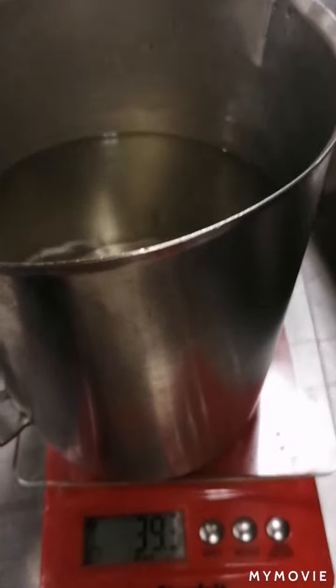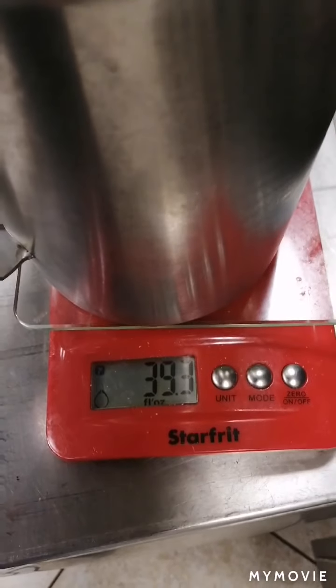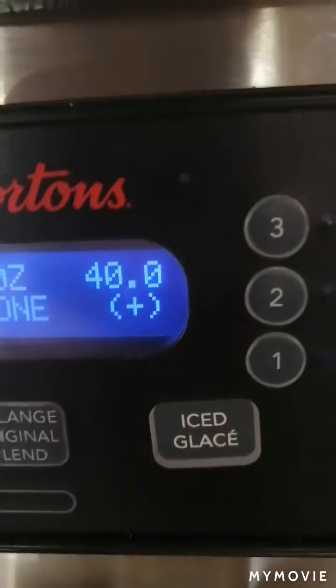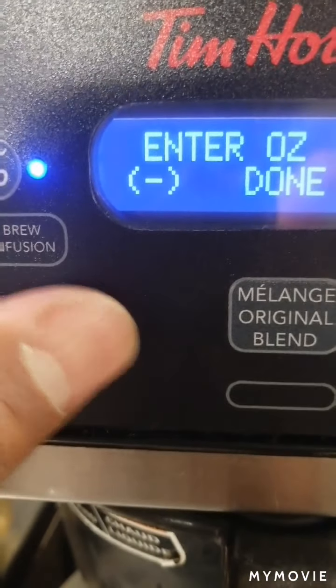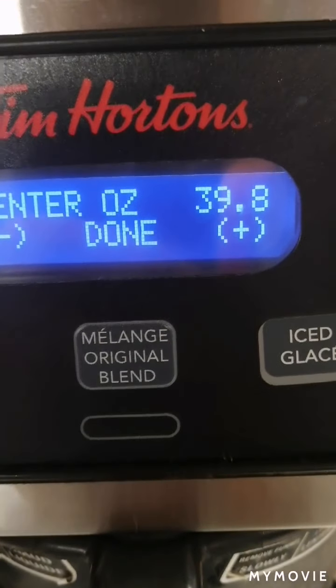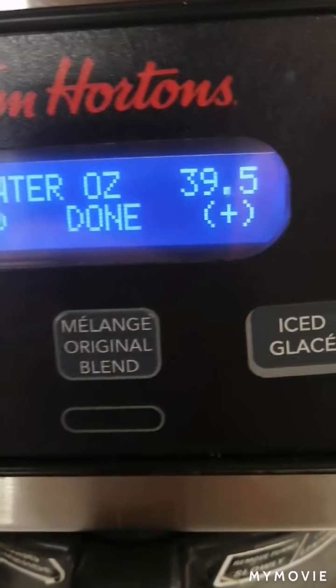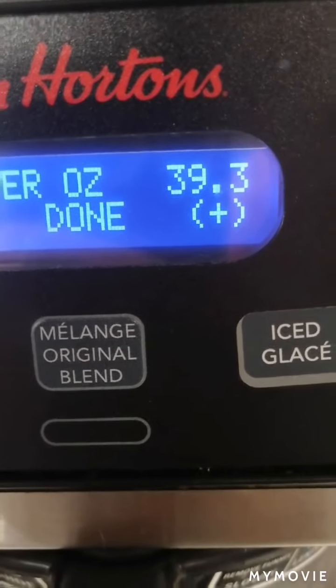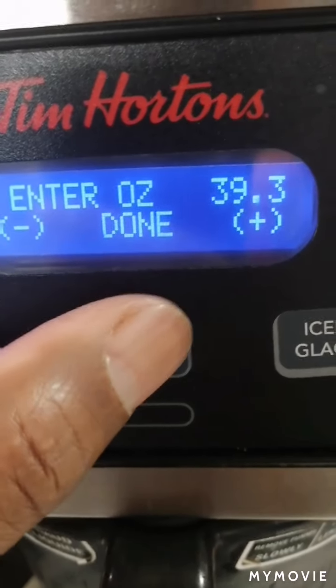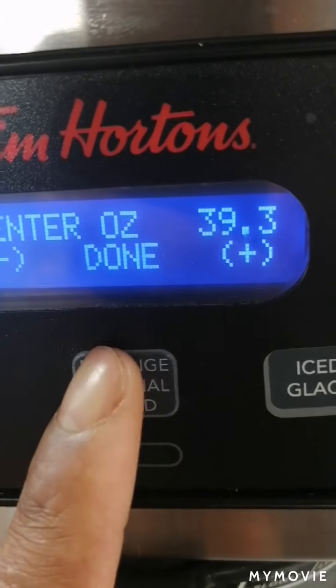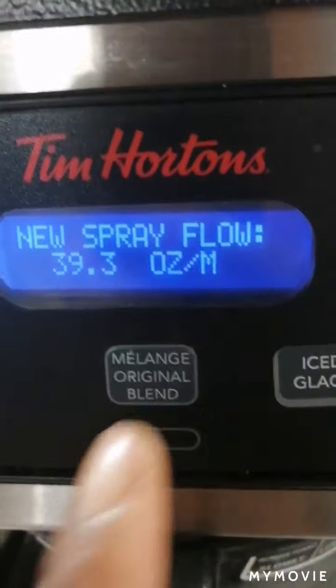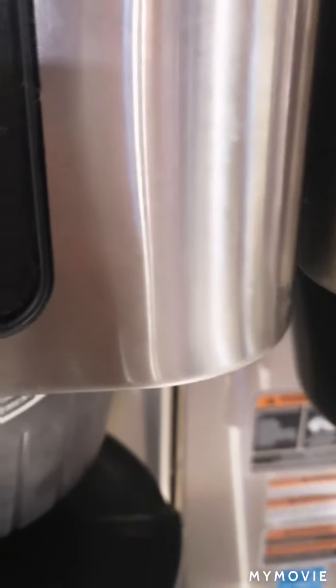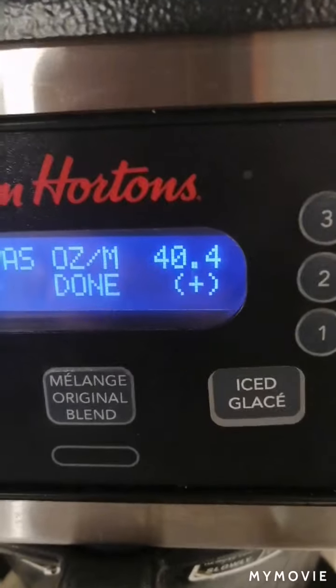So the scale is telling me that it gives 39.3 ounce, and that's fluid ounce, and the machine is telling me that it gives 40 ounce. So I need to minus. I'll hold this button down, there you go, 39.8, 39.7, 39.6, 39.5, 39.4, 39.3. So I get that amount that I have in the picture, and now I'll select the original button to save that. So I already saved it, so I'll dump the water that I have in the graduated cylinder, and now I'll move on to the bypass.